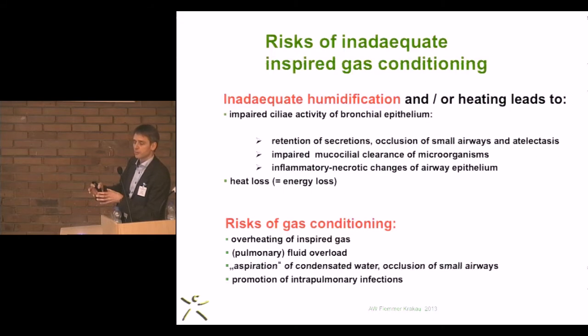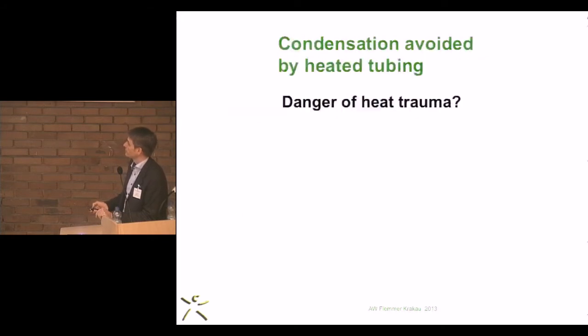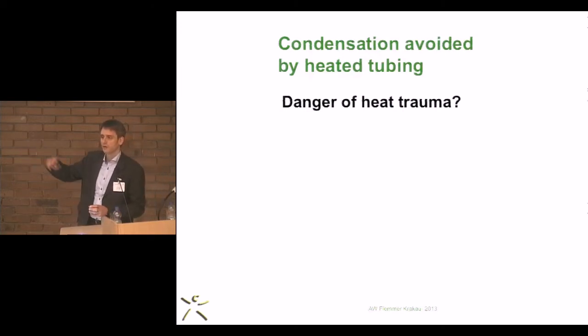Let's say if you're heating your chamber up to 40 degrees, 100% humidity, then you might have rain out in the endotracheal tube or the trachea, because then at 37 degrees you have rain out that might lead to aspiration of condensed water and subsequent occlusion of small airways, and again promoting intrapulmonary infections. So the question is, how about the danger of increasing the temperature of your ventilatory tubing? Because the setting in a Fisher and Paykel heating humidification chamber actually is that the chamber itself heats the water to 37 degrees in order to achieve 100% relative humidity.